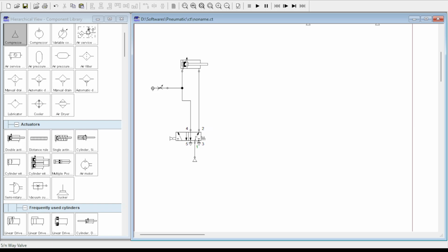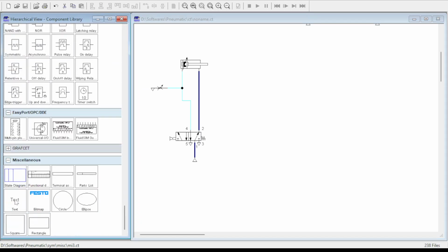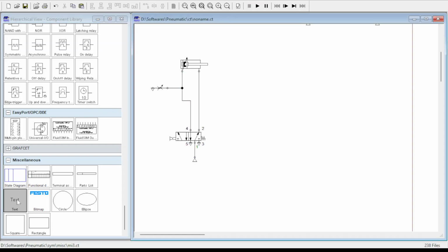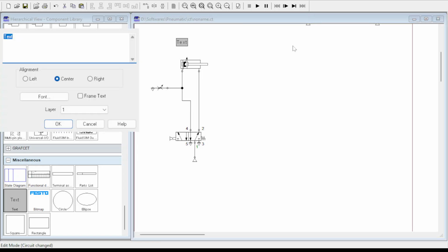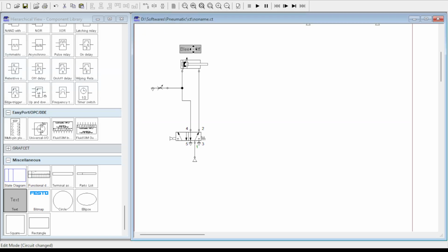By moving the piston. And so when I actuate, the flow entering into the cylinder or coming out of the cylinder will also find a path which will escape out through the throttle valve into the atmosphere. Thereby, the compressed air stream is bled off from the working fluid stream. Thereby, the speed of actuation can be controlled.